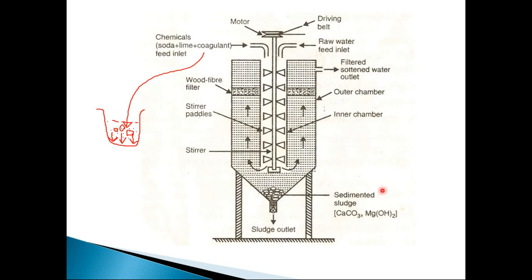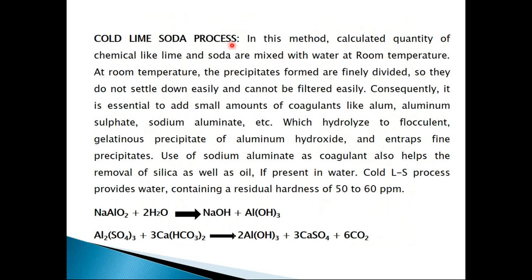In the cold lime-soda process, a calculated quantity of lime and soda are mixed with water at room temperature. At room temperature, the precipitates formed are finely divided and do not settle down easily and cannot be filtered. Consequently, it is essential to add small amounts of coagulant like alum, aluminum sulfate, or sodium aluminate. These hydrolyze to form a flocculant gelatinous precipitate of aluminum hydroxide which entraps the fine particles, causing them to grow in size and settle down as sludge.